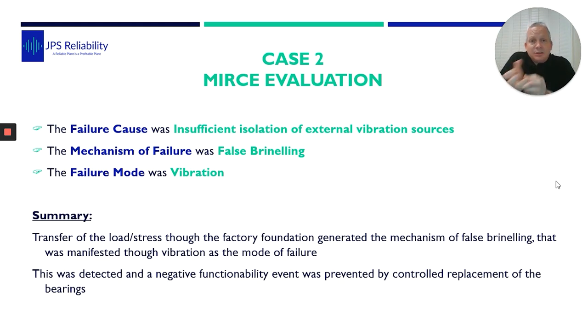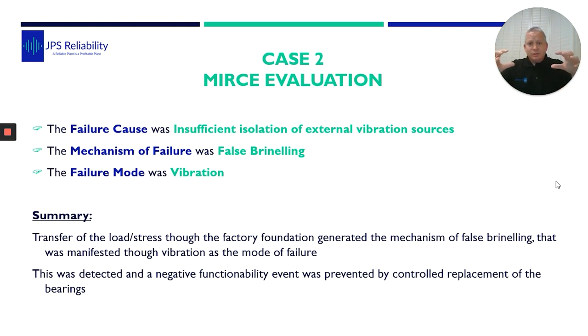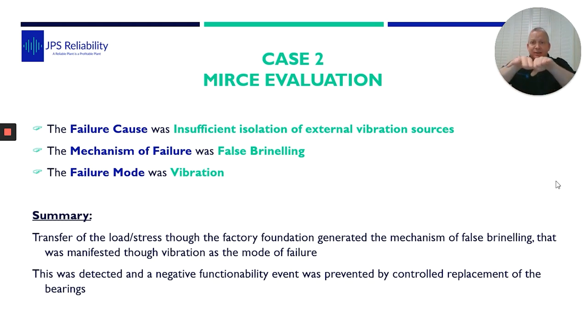The mode of detection — the failure mode — was through vibration. You can put in there as well audible noise, because obviously they heard it too. The summary on this case is that transfer of load and stresses through the factory and foundation generated the mechanism of failure of false brinelling, which manifested itself in the vibration mode of failure. This was detected, and the negative functionability event was prevented — we've prevented an event which affects the functionability of the system. It is managed and controlled.